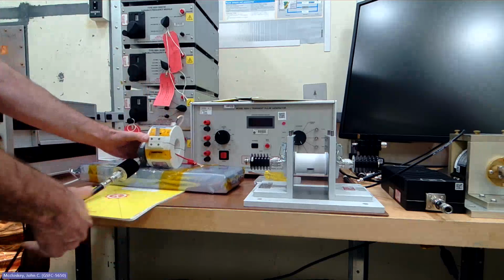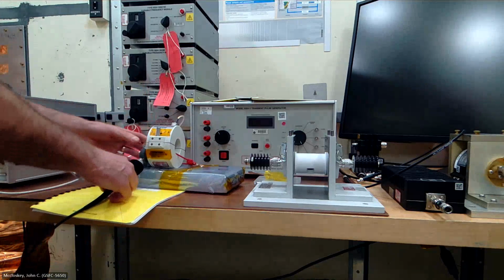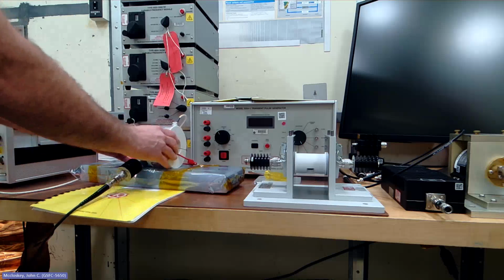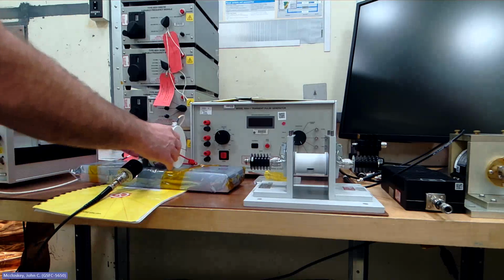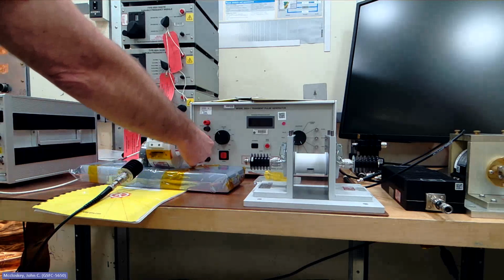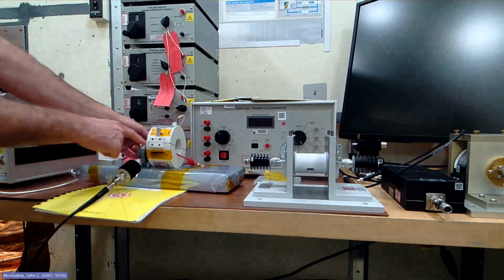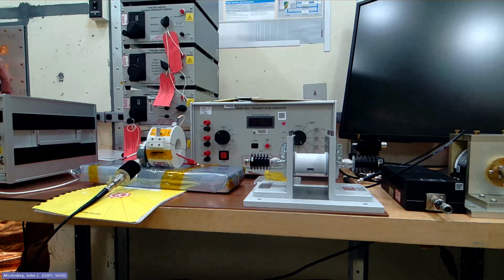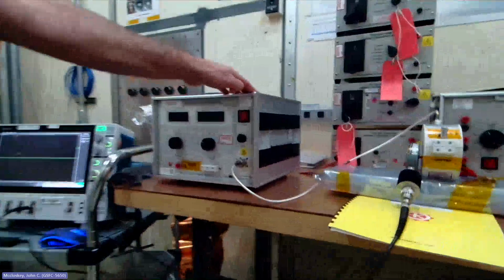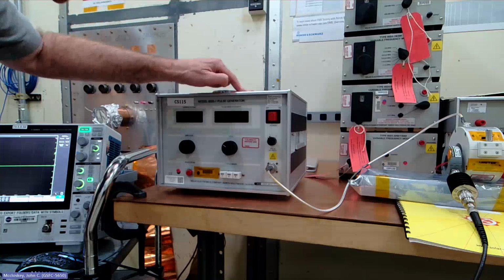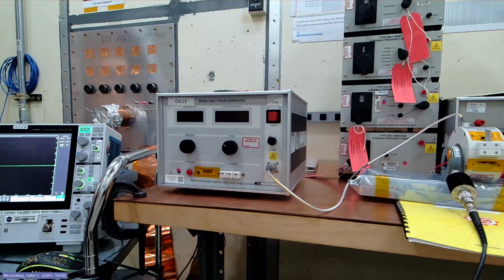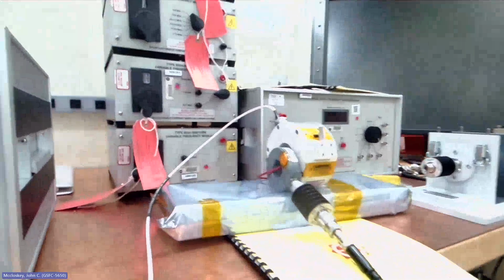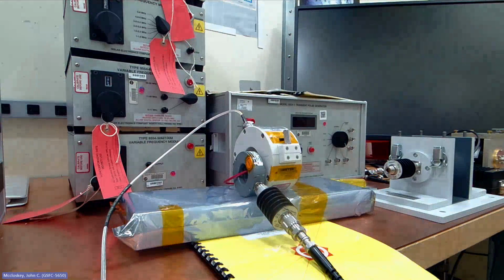So just generally good practice to not have metal touching the ground plane here. You can help it, so I'm just insulating things from the ground plane a little bit here. So we're injecting onto our loop of wire, and then we're going to monitor the current. And I've left the signal generator alone. The pre-calibrated level should be... sorry, I'm looking at the wrong one. There we go. I've left the signal generator settings alone. So when we turn it on, it should come up to the same level that we pre-calibrated it to. So one more look over here at what we're injecting, and then we'll turn on. We'll look at the scope.